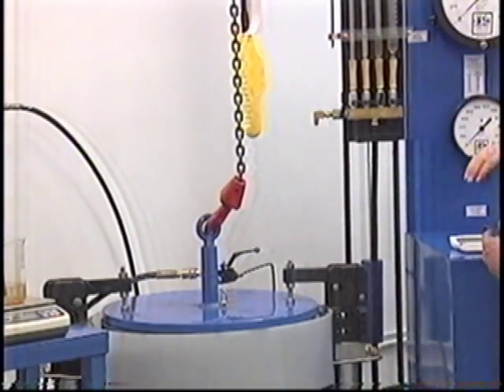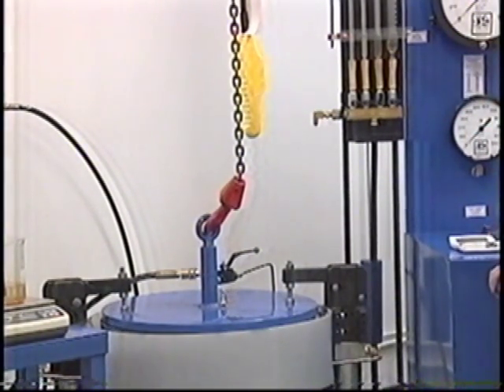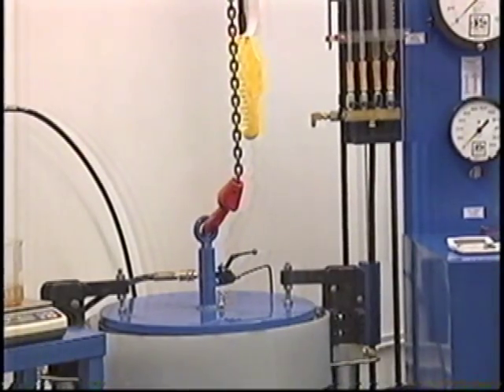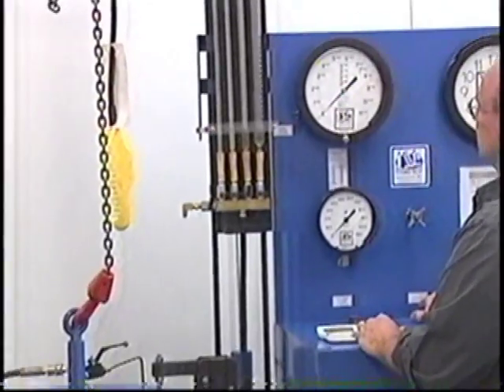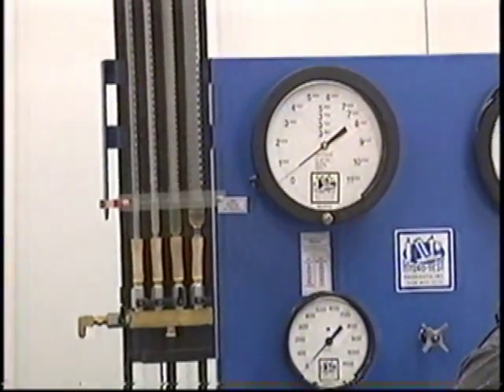Again we get that slight rise of expansion, which is the city water pressure. That is the beginning of the test. You do not want to disturb that. At this point we are going to then just go right up to 5000 psi on our pressure gauge.